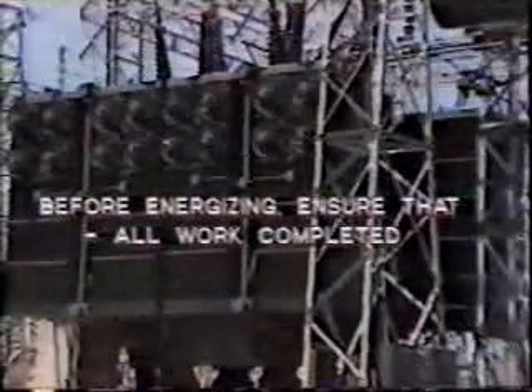Before energizing, they will make sure that all work has been completed, that all temporary grounds are removed, and that all permits to work are cleared. All protection relays should be in service, even though further adjustments may have to be made. Indeed, for the first energization, the protective relays may sometimes be temporarily set to give increased sensitivity.